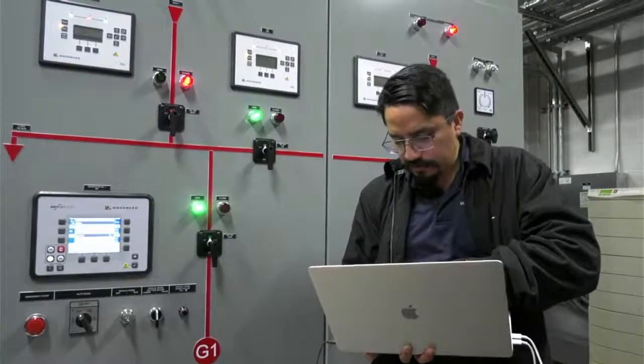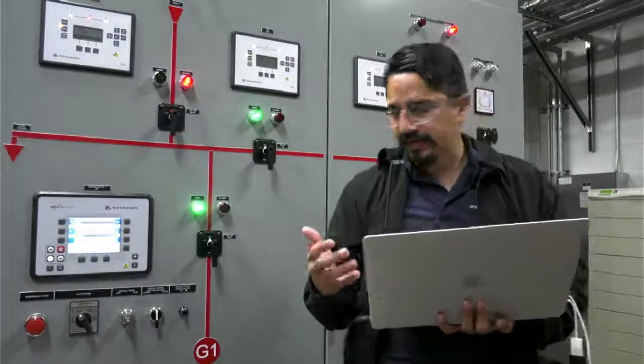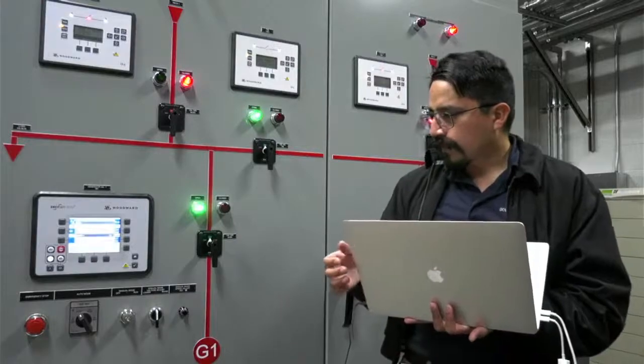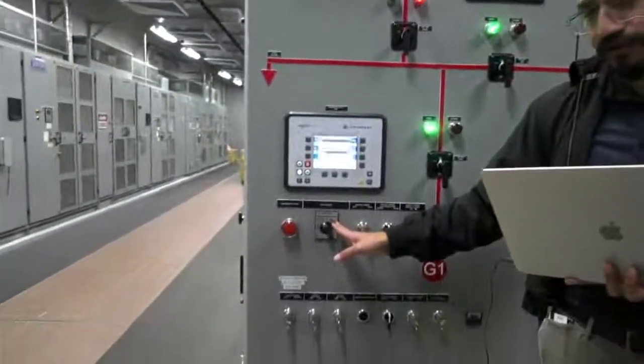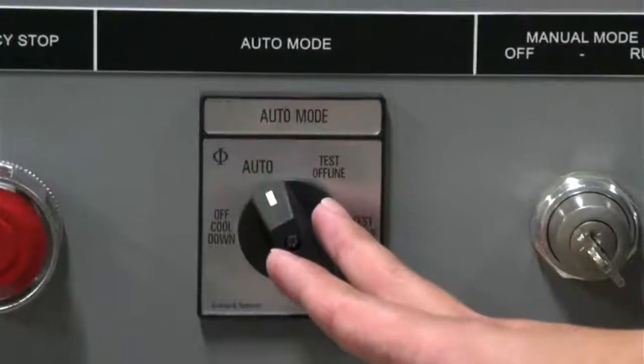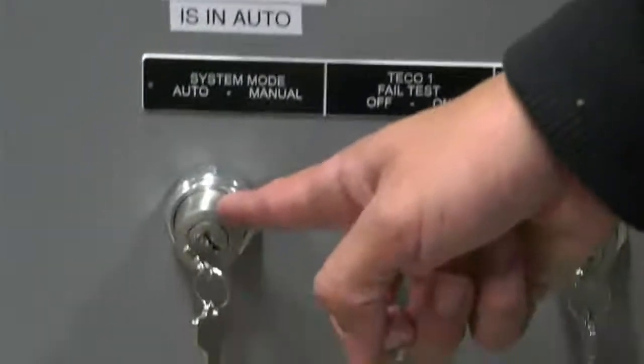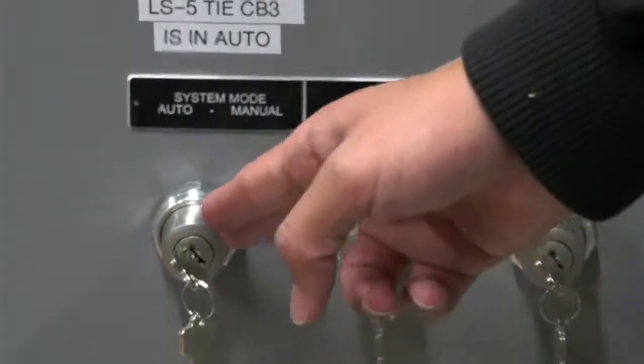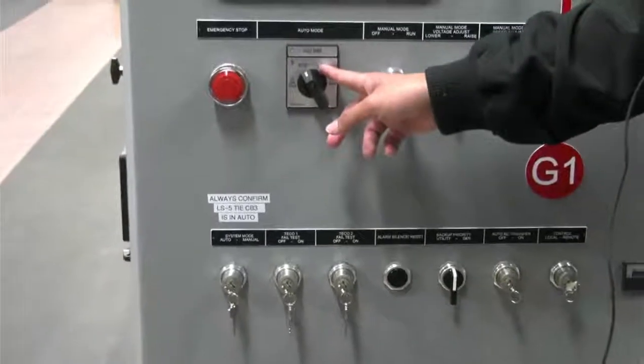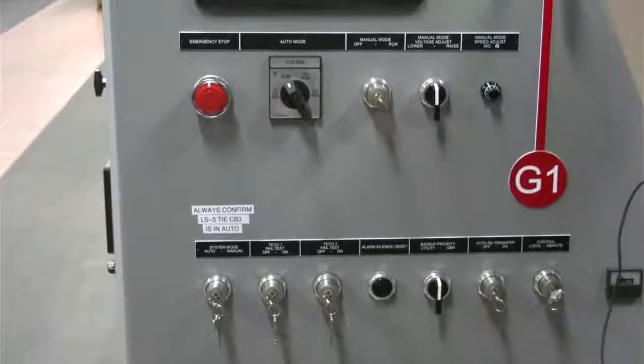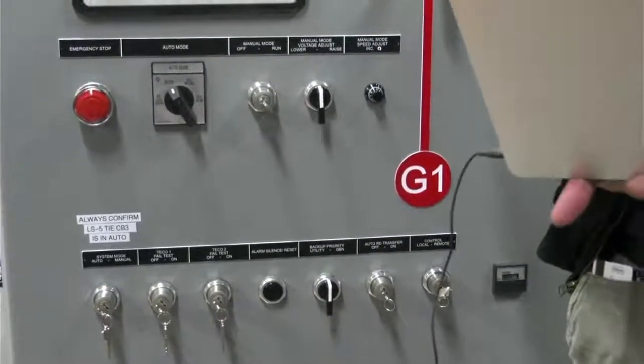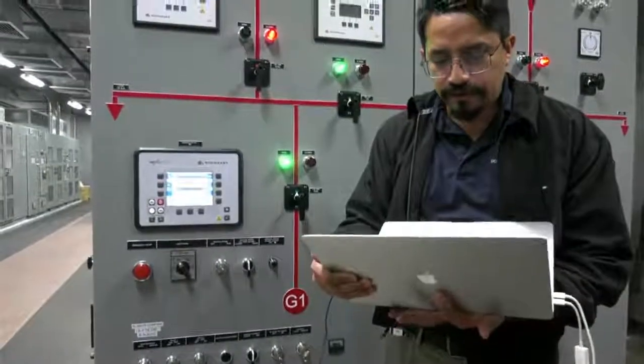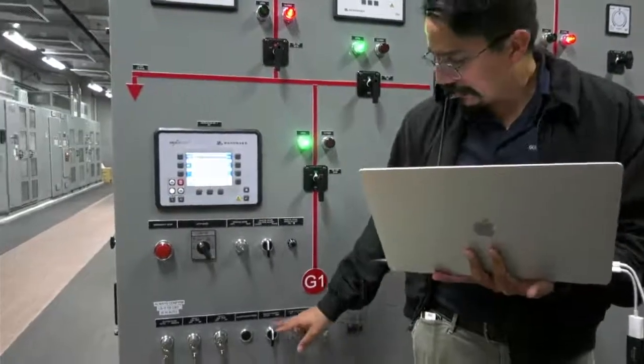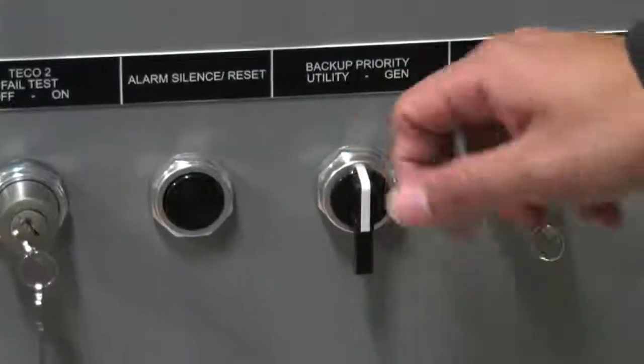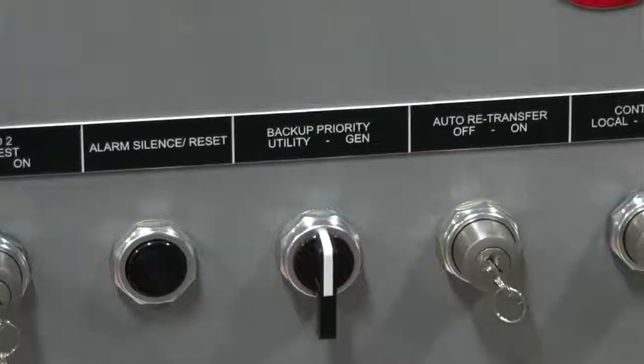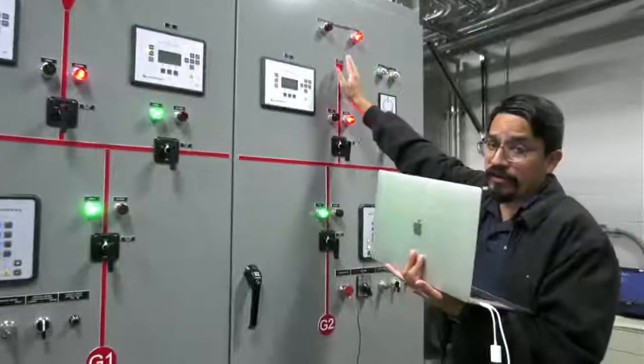So now we're going to talk about the tests that you can apply to the system. We have mainly this switch over here to do the tests, and to be able to use this switch, as I said before, we need to have the main switch on auto. Having the main switch on auto, we can go here and do a test offline or test online. Let's talk about the test online first. I'm on sheet 42. So, first of all, we need to set the priority to generators to do any tests. Right? So we change this. If it's on utilities, we go to generators and we confirm here with the pilot lights we are on generators.